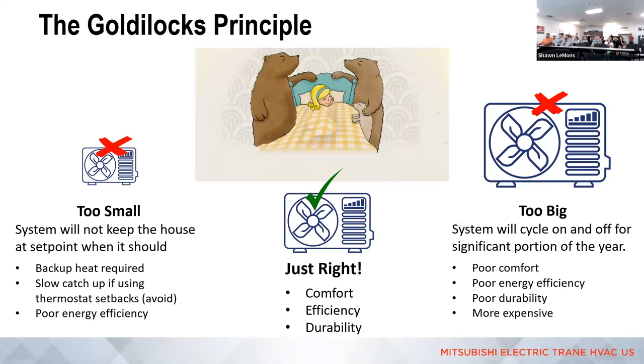We're looking for that Goldilocks zone, and there are reasons for that in terms of efficiency and durability. Yes, these systems are variable, but not infinitely variable from 0% to 100%. You're generally going to find operation from maybe 20-25% up to 100%, depending on the need. So we do need to think more specifically about sizing. That does matter. We have some flexibility, but finding that Goldilocks zone does matter.